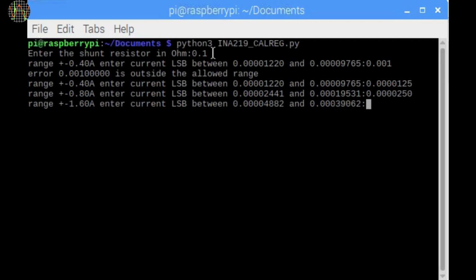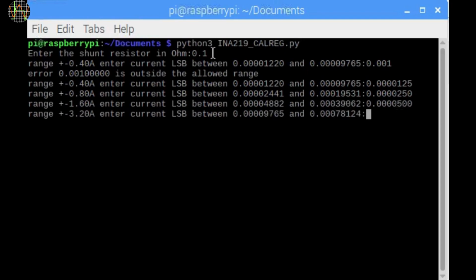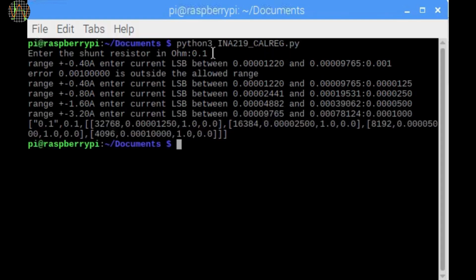For the 1.6 amp range I picked 50 microamps. And for the last range of 3.2 amps I picked 100 microamps. The program then spits out the default calibration configuration data in a format you can directly use as a line in the cal data file.